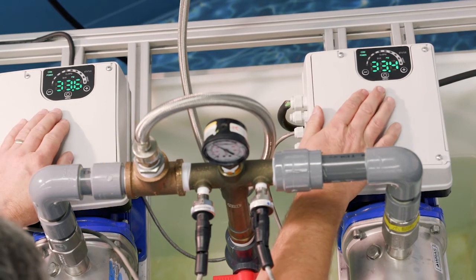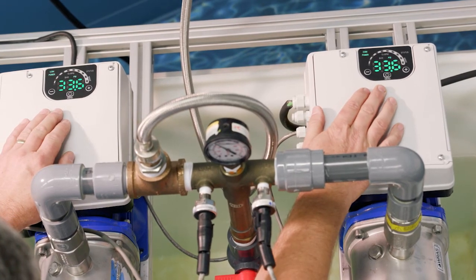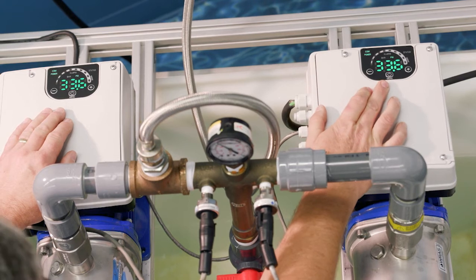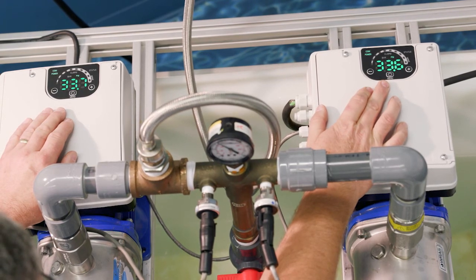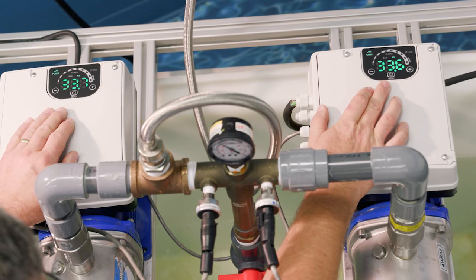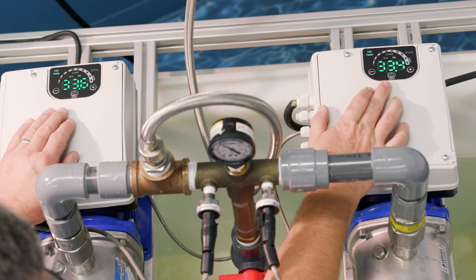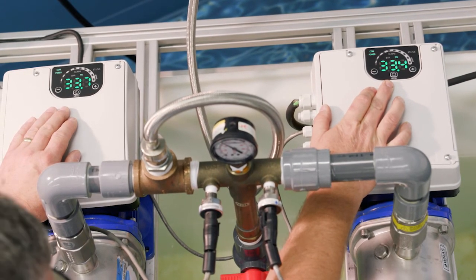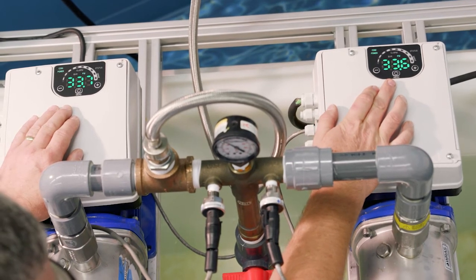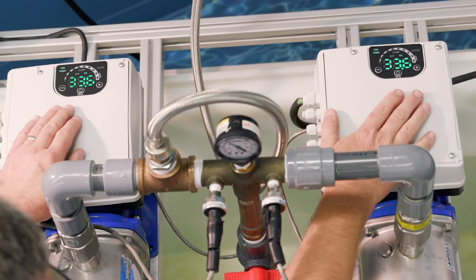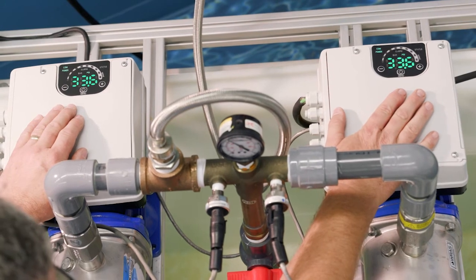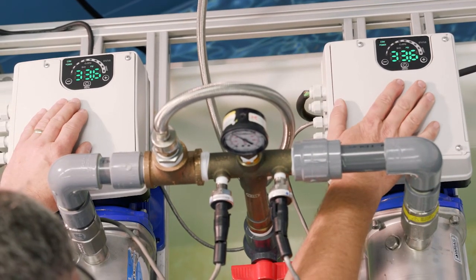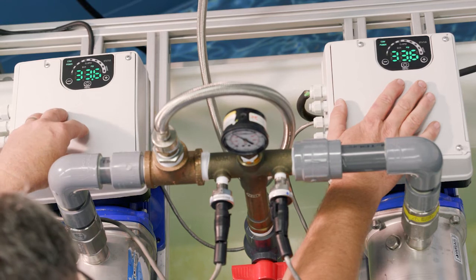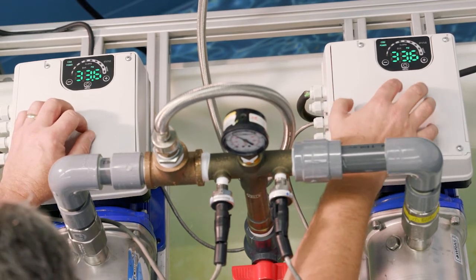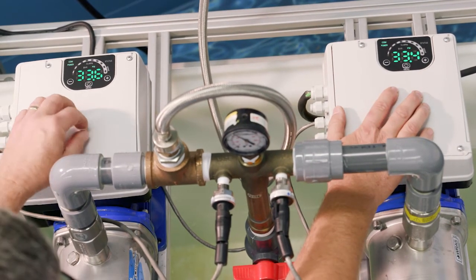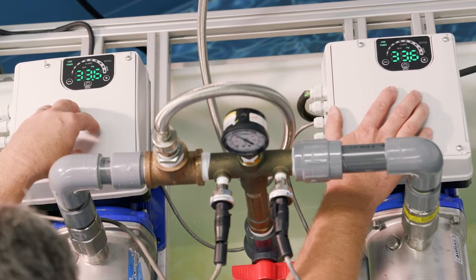And how we left it was multi-pump synchronous. So on your display, it's going to show up as an N, as in Nancy, but it's really an M if you look up in the manual. So that's multi-pump, SY is synchronous. So synchronous basically means that when one pump cannot maintain the set pressure at full speed, it calls on the lag pump. And in this case here, this is going to be our lead, the one on the right, and the lag is the one on the left.